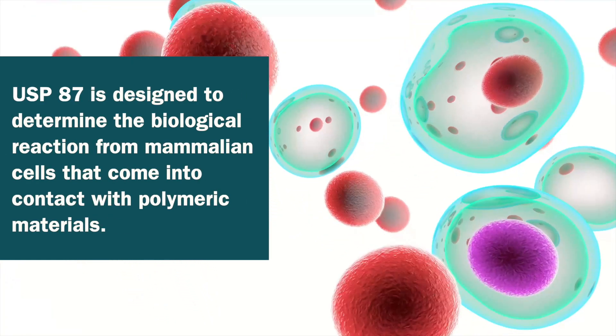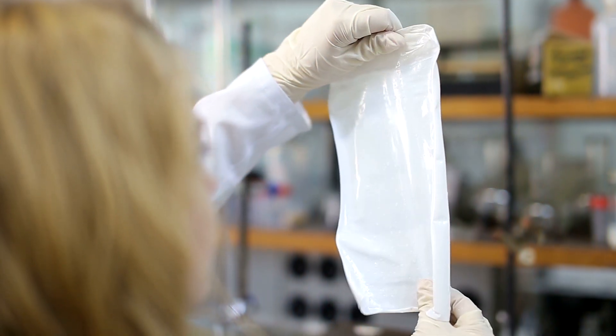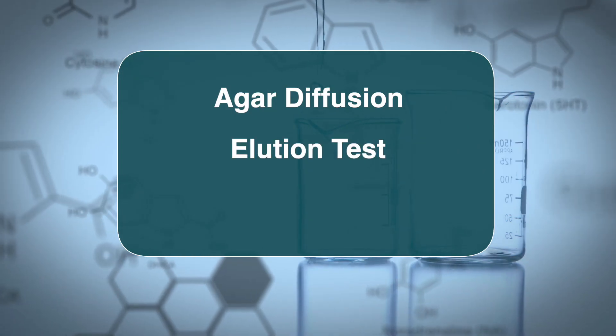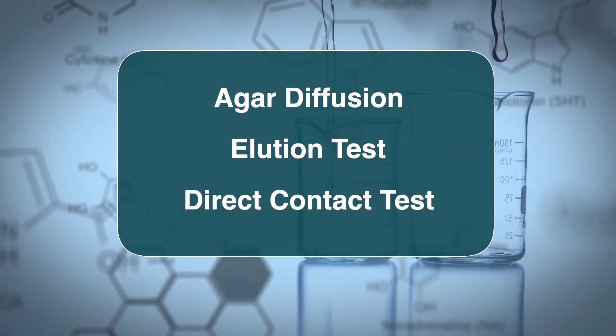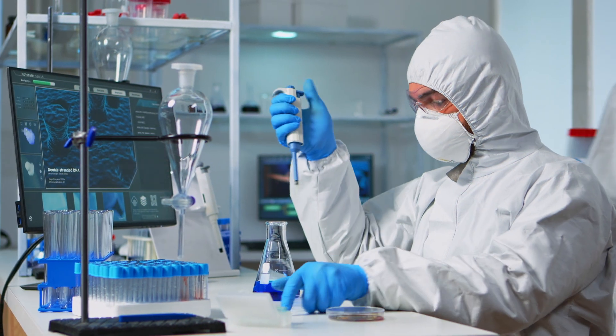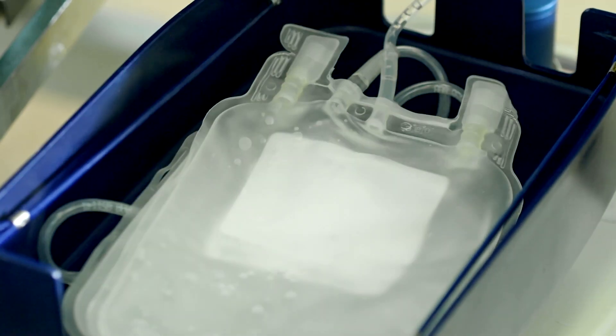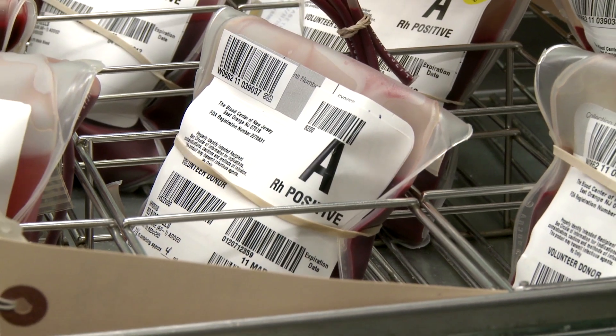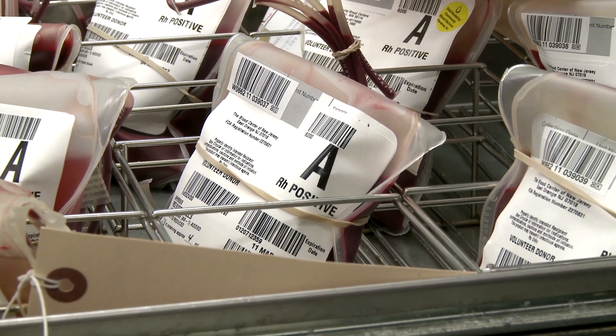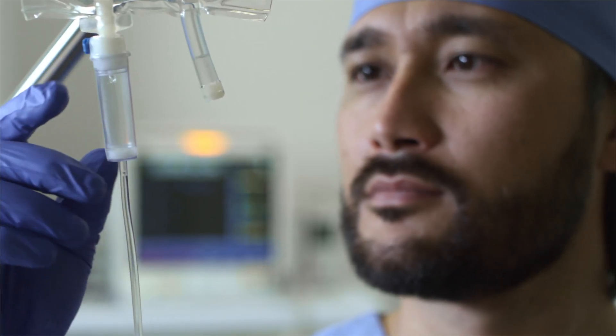USP-87 is designed to determine the biological reaction from mammalian cells that come into contact with polymeric materials. USP-87 uses three distinct test methods: agar diffusion, elution test, and direct contact. The decision as to which type of test depends upon the material, the final product, and its intended use. These uses may include plastics or elastomers used as containers or used to seal containers that will hold drugs or other solutions for intravenous bags, intravenous tubing, or any other plastics that will directly contact the patient.